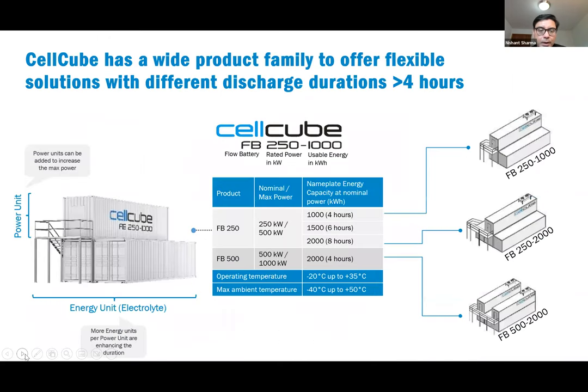Next slide. Our basic building block starts with 4-hour systems—we could do 4, 8, 10, 12 hours, you name it. The energy rating of the battery system is dictated by the electrolyte, which you see in the bottom containers, and the power capability of the CellCube comes from the power stacks, the top container. So the more energy you need, the more electrolyte tanks you need—that's how the scaling of the system works.